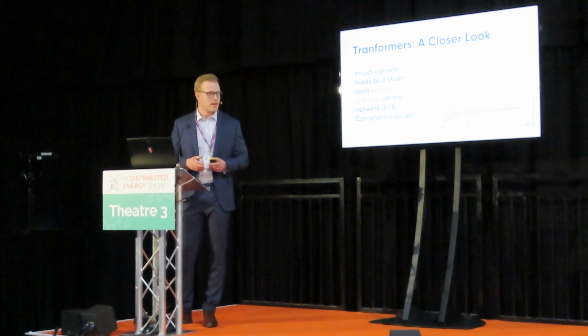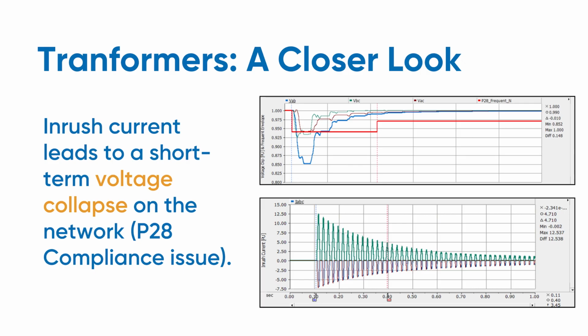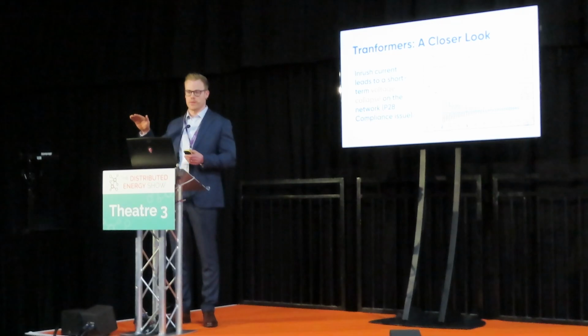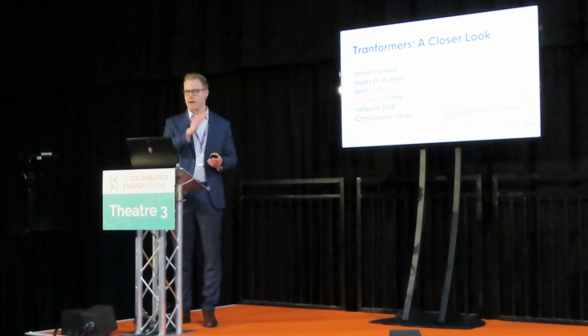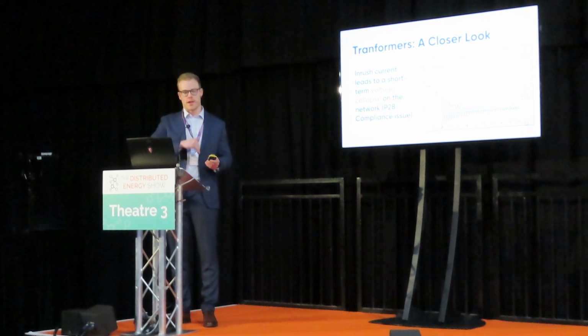This is what it looks like. The graph on the bottom is a typical inrush current trace of a transformer that's just been energized. As you can see, it goes from zero current to a very high peak, and it then decays down. That's all done in around a second, which you'd think is not a problem. But as you can see, the top graph is the voltage at the connection point that we've just energized that transformer on. Effectively, 1 per unit is the ideal voltage that we're looking for. And it causes a massive collapse in the voltage, which then recovers.